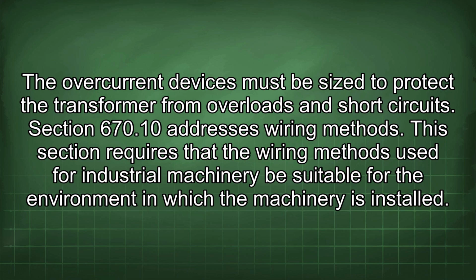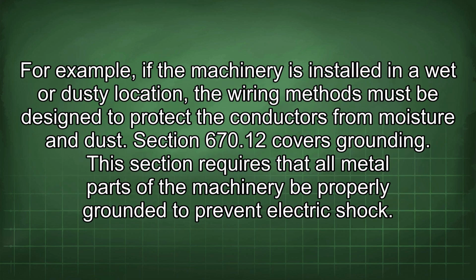Section 670.10 addresses wiring methods. This section requires that the wiring methods used for industrial machinery be suitable for the environment in which the machinery is installed. For example, if the machinery is installed in a wet or dusty location, the wiring methods must be designed to protect the conductors from moisture and dust.